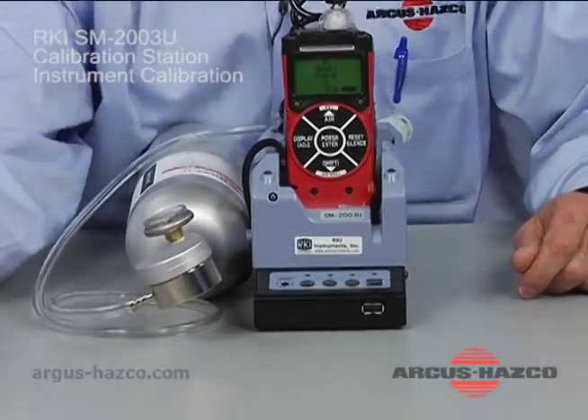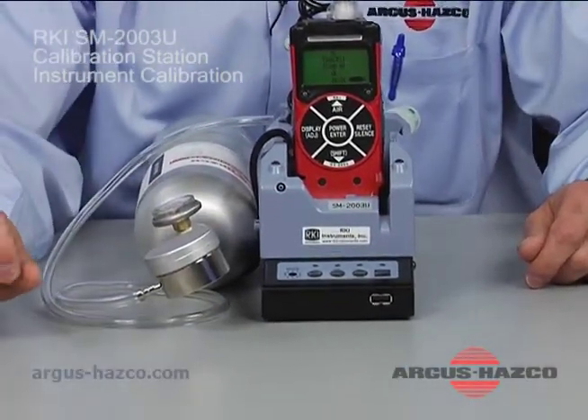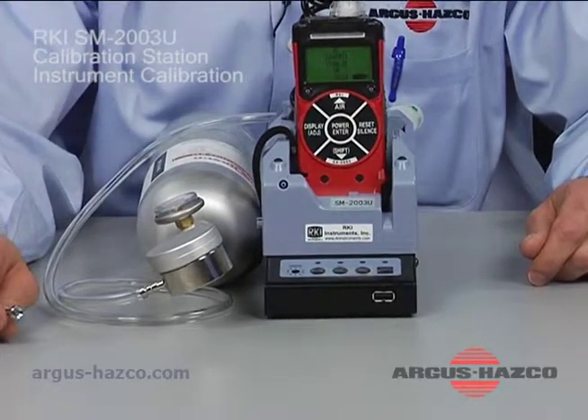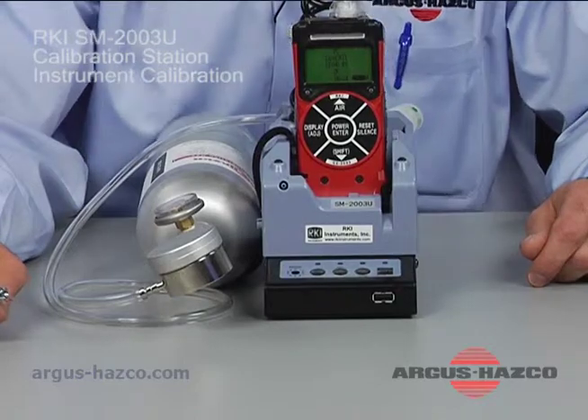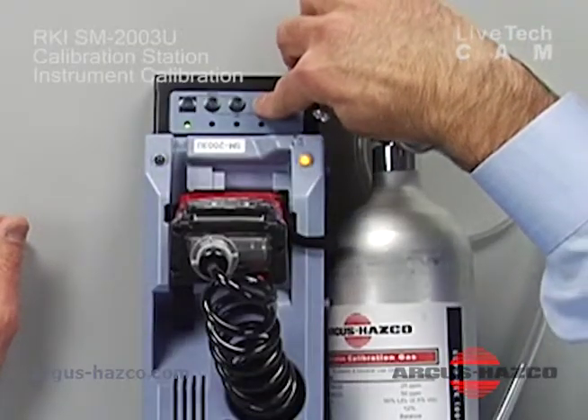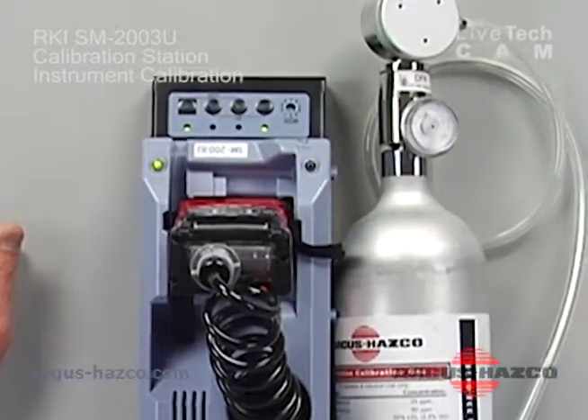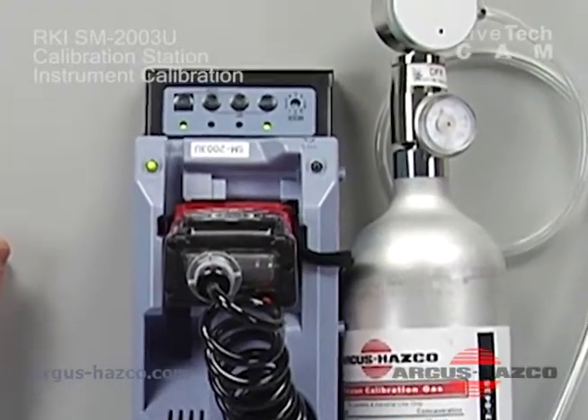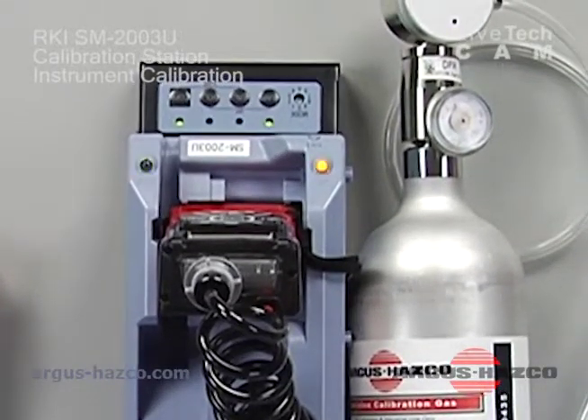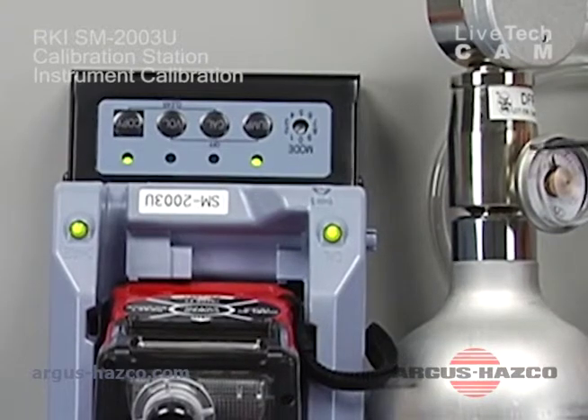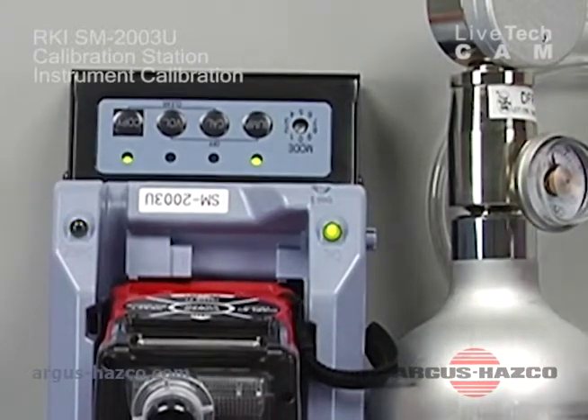If you were to bump the instrument, and for most cases, as I understand it, Ford has a protocol to bump or challenge the instrument upon every use. So if you were to push the bump button, you'll see it start to flash. That indicates that there is gas flowing to the instrument. And the process, if you're just bumping, should take about 1 minute and 15 seconds. The instrument, when it completes its function, will indicate to you if it's passed or failed.